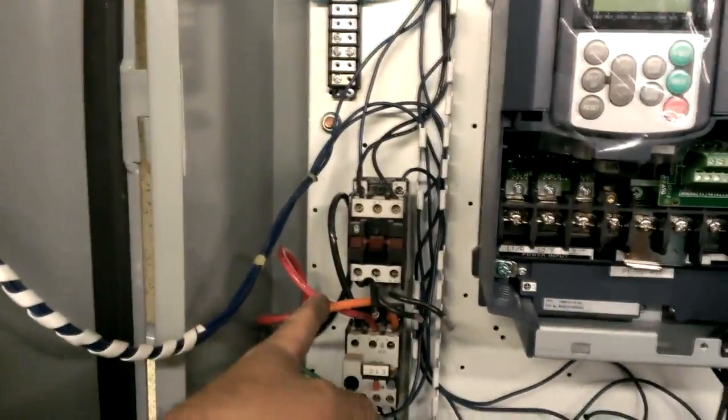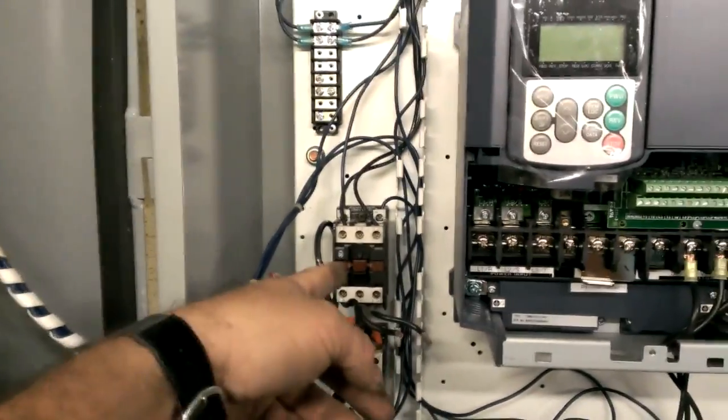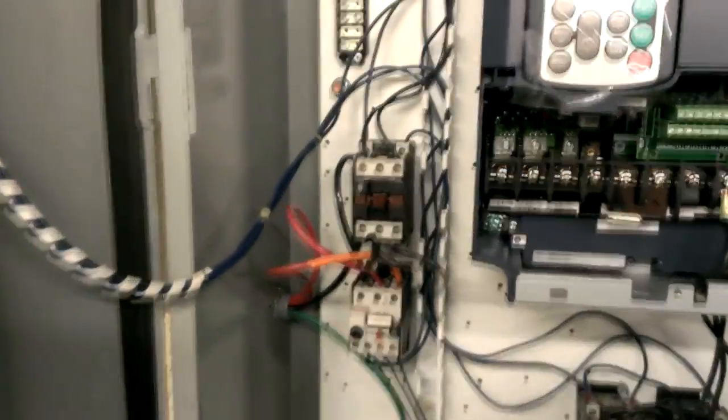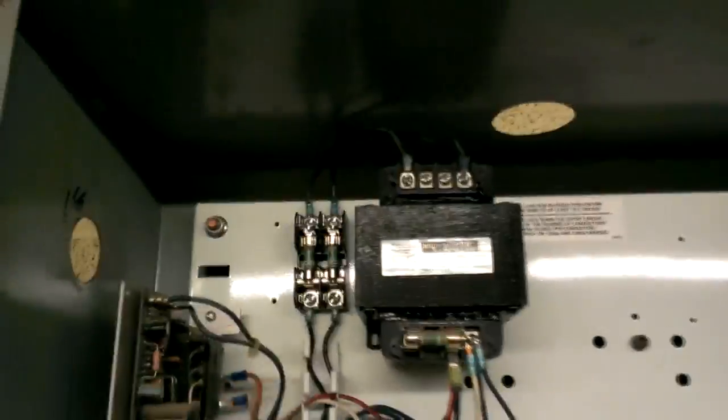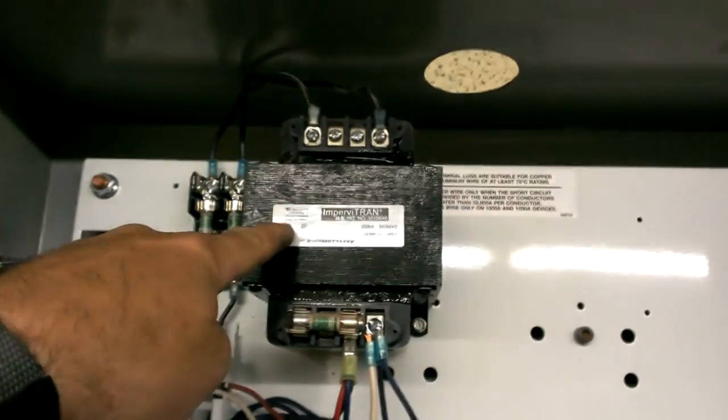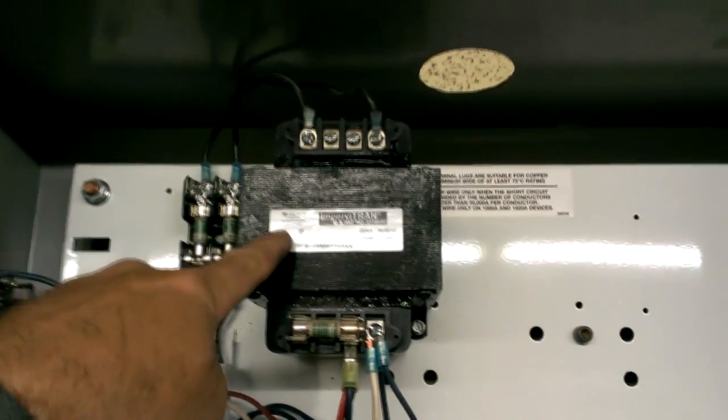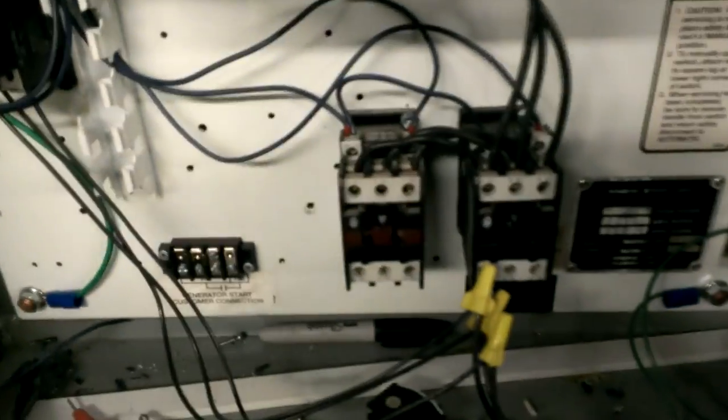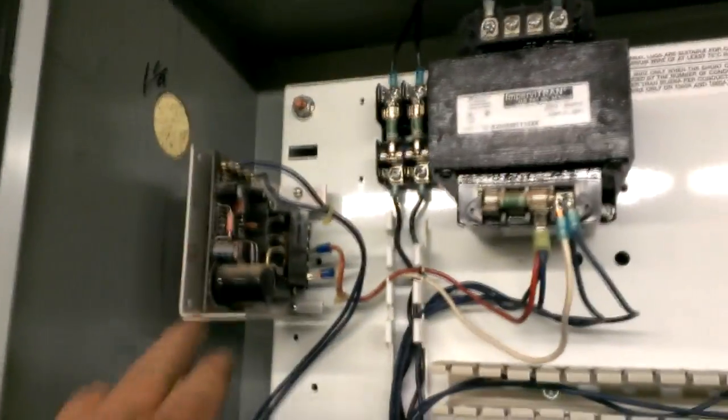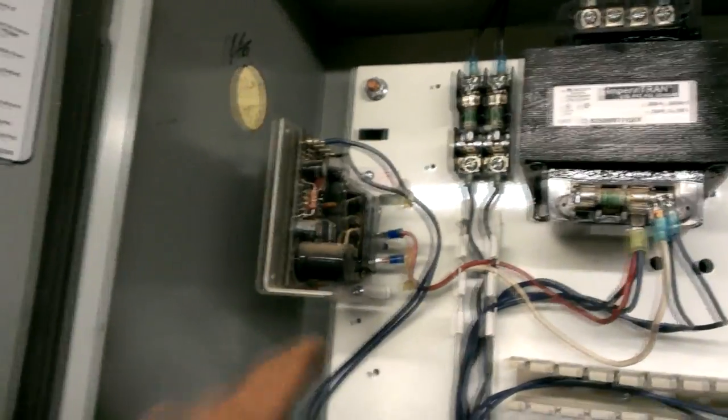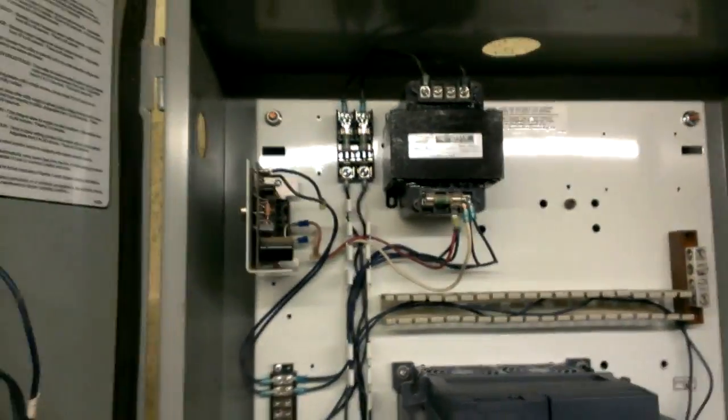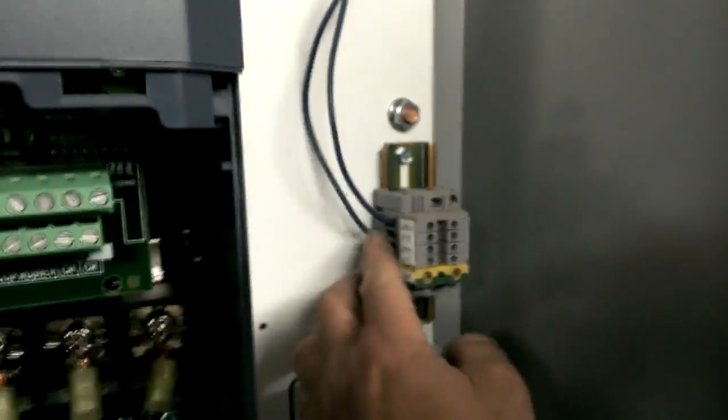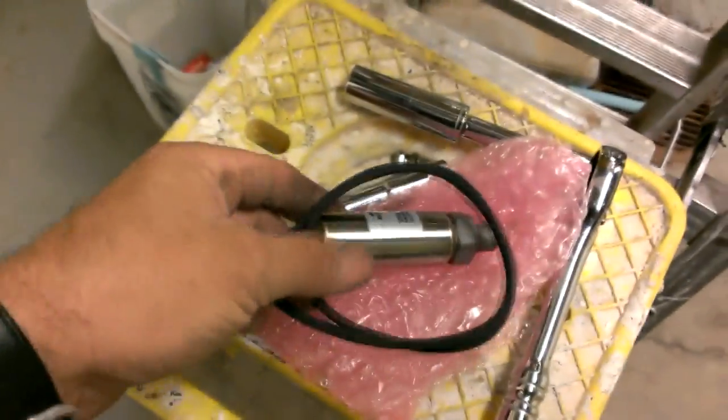This is the incoming power here. This will interrupt a current overload. 480 to 120 volt step down transformer for the contactors, continuous duty contactors, and then this is a 24 volt DC power supply. It's recycled that out of the other control, so that's what's going to go and feed the pressure sensor, which just came in.